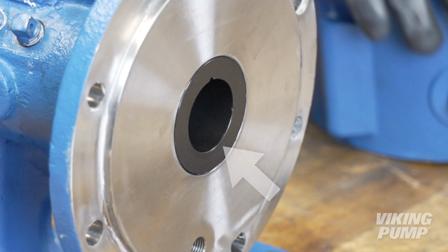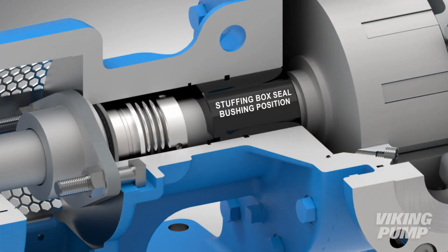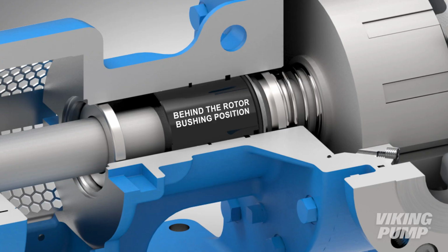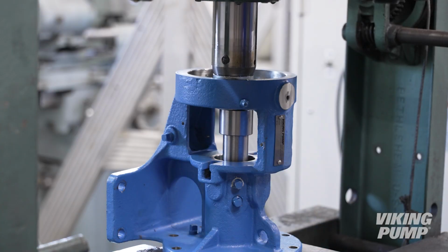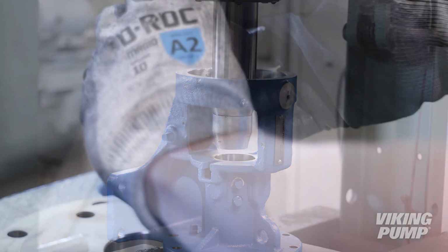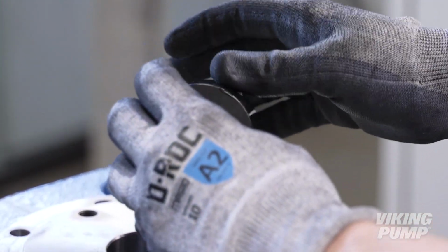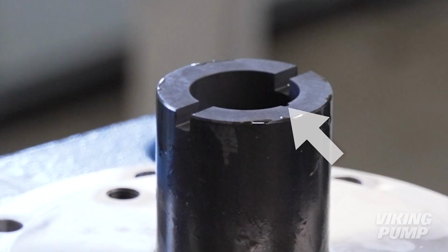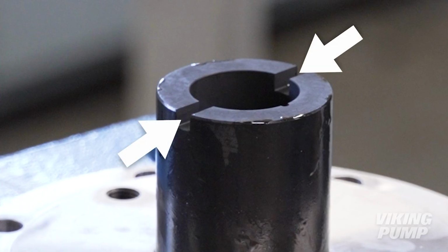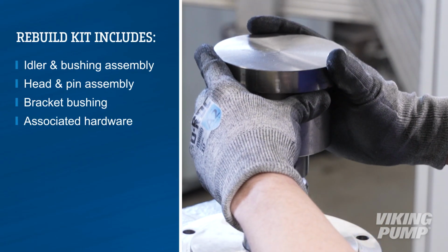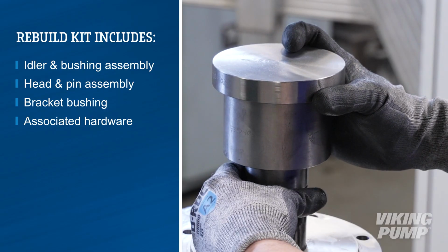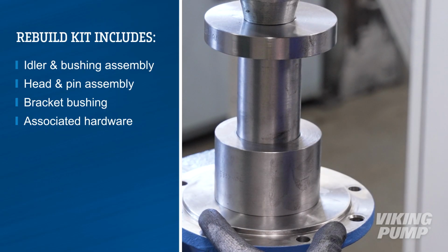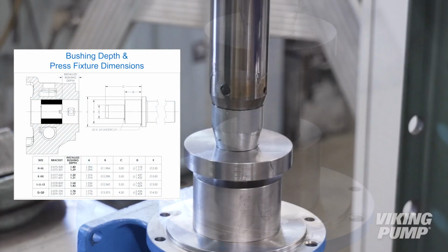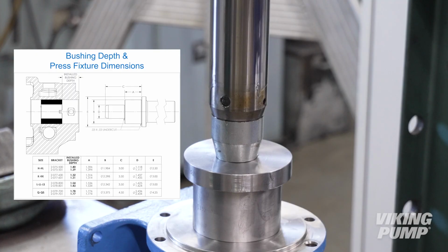At this point, the bushing will need to be removed and a new bushing installed in the behind the rotor seal position. Using a hydraulic press, carefully press out the old bushing. When installing, use care to avoid breaking or damaging the carbon graphite bushing. Bushings with lubrication grooves should be installed with the groove at the 12 o'clock position and the notches facing the head end of the pump at the 3 and 9 o'clock positions. Lubricate the bushing and ensure it is started straight. Bushings in the behind the rotor seal configuration need to be pressed to the appropriate depth. Please refer to the technical service manual to confirm proper bushing depth for your pump size.